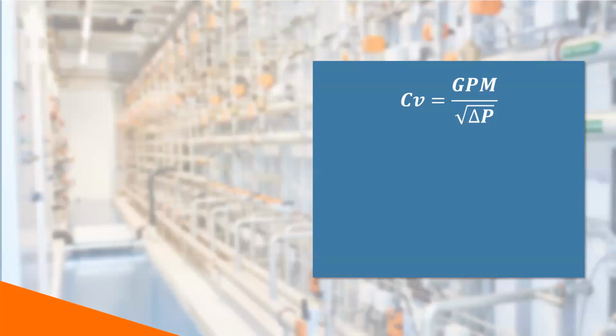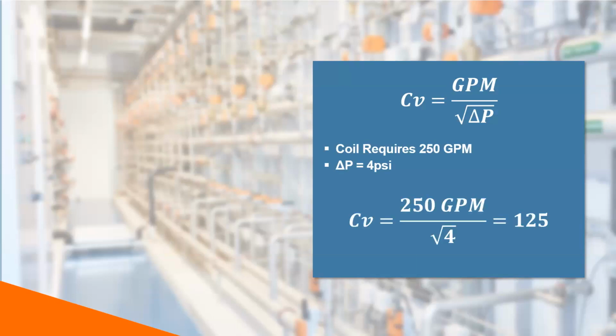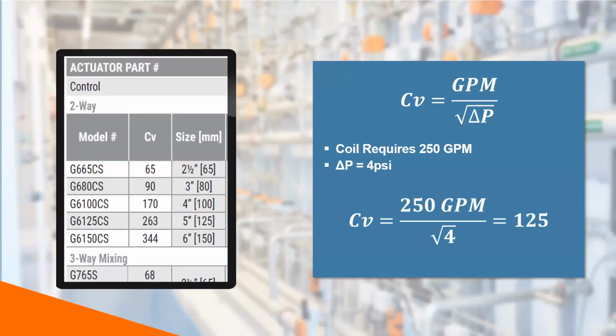At Belimo, we utilize 4, and that's what we're going to utilize for this example. The square root of 4 is 2. So your CV is essentially half of your GPM. So if we have a coil that requires 250 GPM with a 4-pound pressure drop, we have a CV of 125. What happens is that contractor will go to a catalog, and here is a page from the Belimo catalog, and you will see our first problem. We do not have a valve with a 125 CV, but we have 2 valves that we can choose from, one at 90 CV and one at 170 CV. So which one should we choose?